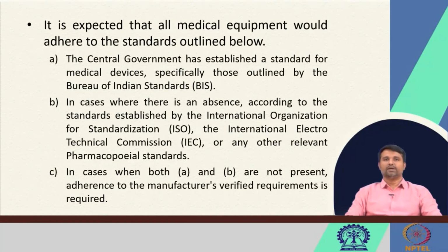In such cases where there is an absence of BIS standards, they have to follow the standards established by the International Organization for Standardization, that is the ISO, or the International Electrotechnical Commission, IEC, or any other relevant pharmacopoeial standards. In cases where both are not present, adherence to manufacturer's verified requirements is required. This is provided in Medical Device Rules of 2017.